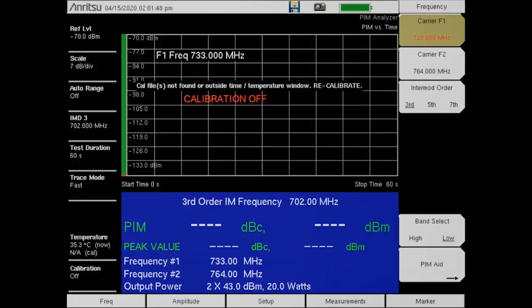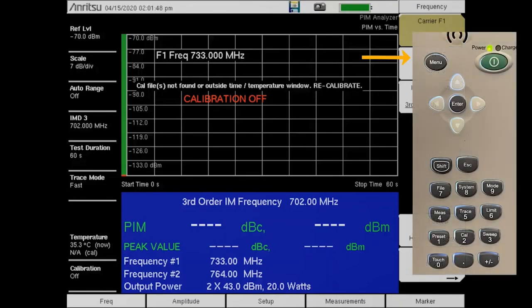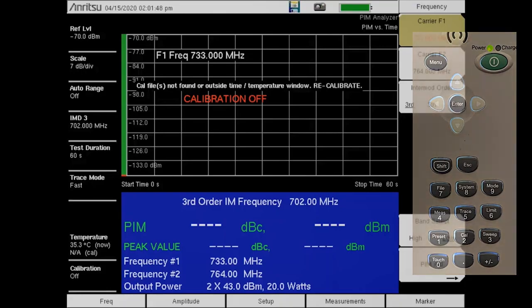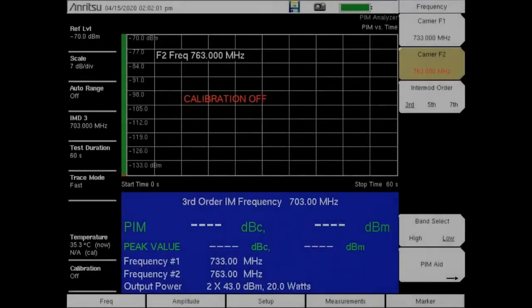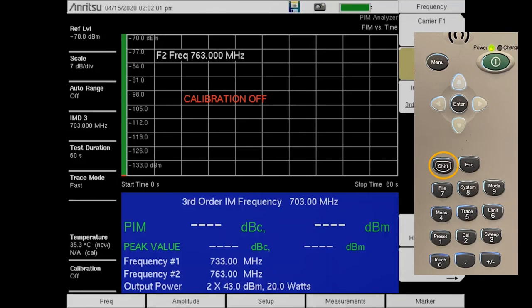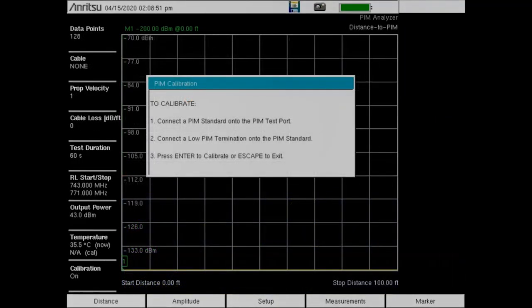Now we will enter a custom frequency for the frequency 2 of 763 MHz. Press the Freq button, followed by the carrier F2 button. From the keypad, enter 763 and then press the megahertz key. With the custom transmit frequencies entered, we can recalibrate. Press the Shift key on the keypad, followed by the Cal key to calibrate. Again, follow the on-screen instructions to complete the calibration and verify that calibration on is now displayed.